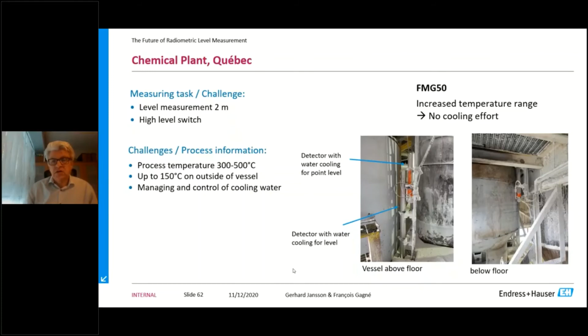The detector is probably something like 8 to 10 inches away, with water cooling. If the water cooling doesn't work as it's supposed to, then you kill the detector, which has actually happened in this particular case. And now we need to replace this. With a new detector that can take a lot higher temperature, we don't really need the water cooling anymore, so that's a cost saving for that particular customer. I don't have a picture of how that worked with the new detector installed.